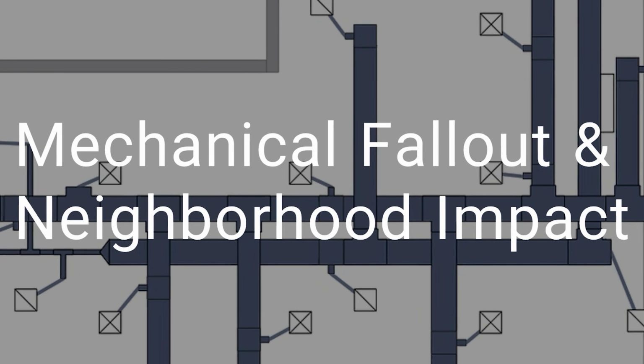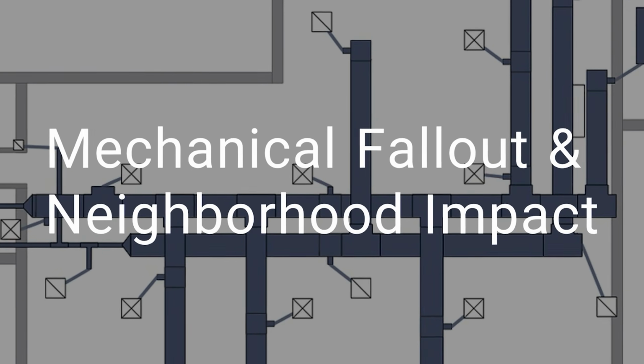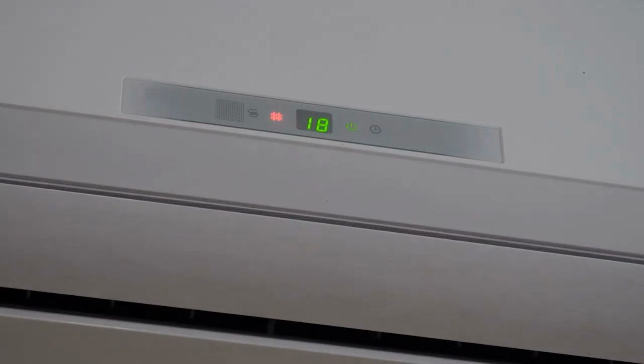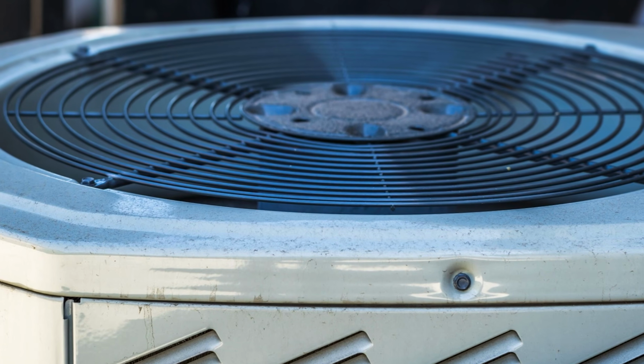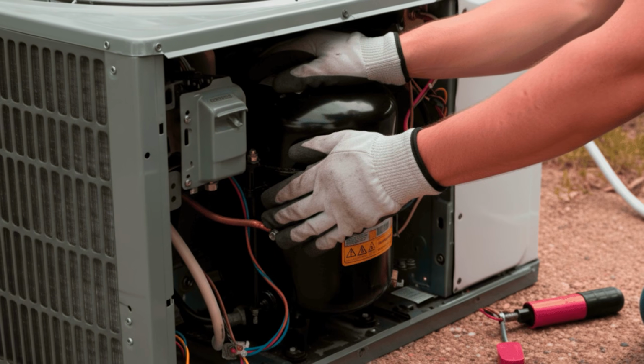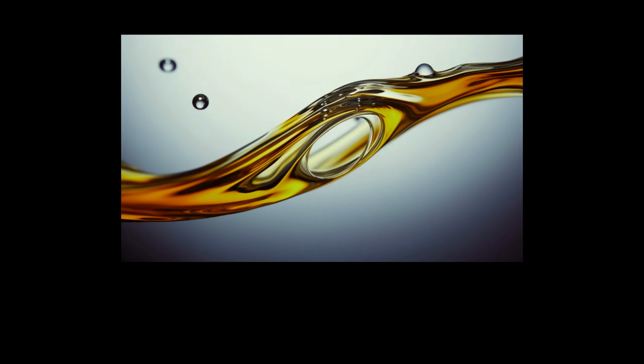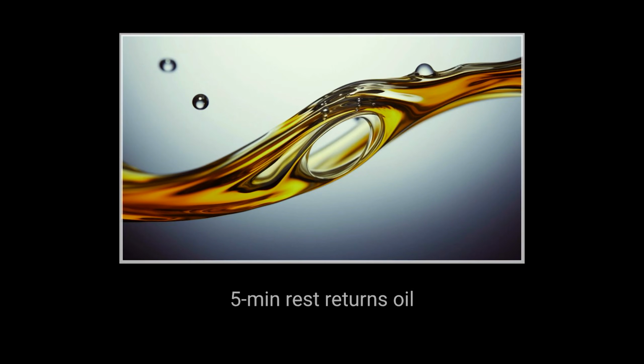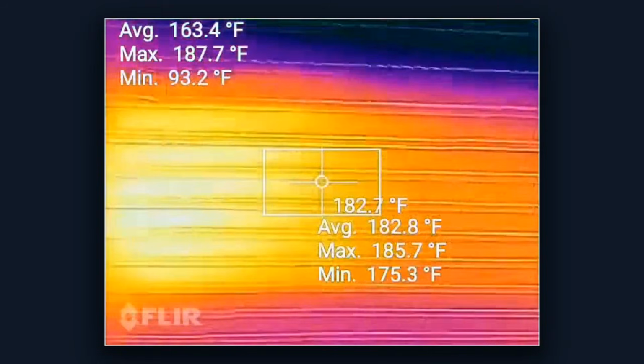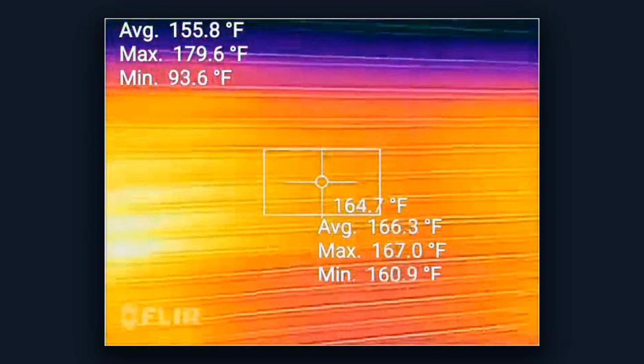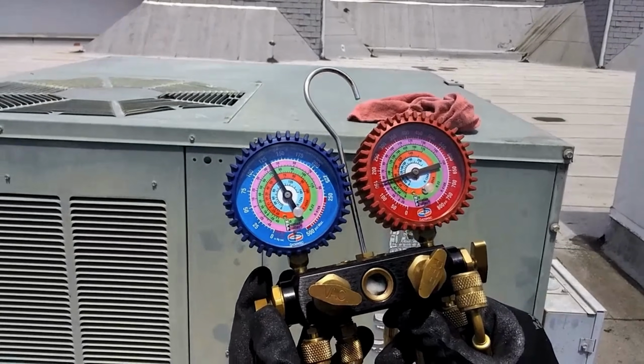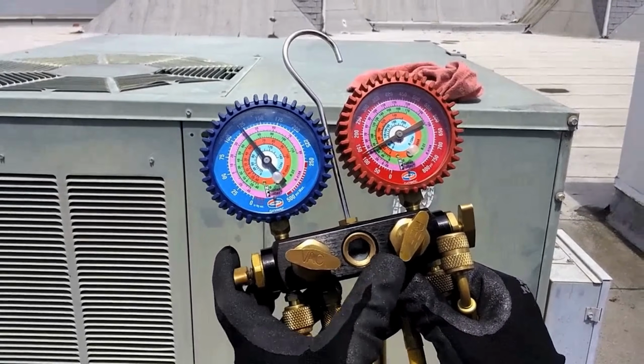Now, let us talk about what happens inside your equipment, because the undersizing is not just a comfort problem, it is a mechanical execution sentence for your compressor. A compressor is designed to run in cycles. It turns on, it cools the space to set point, it turns off, it rests. That rest period is not optional. It is when the lubricating oil redistributes inside the compressor. It is when the electrical windings cool down. It is when the refrigerant pressure equalizes across the system.